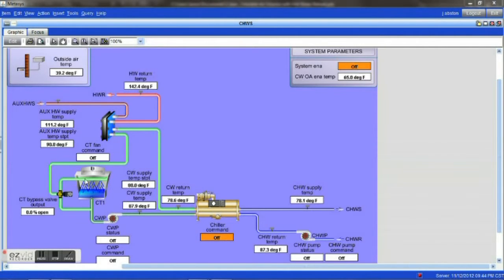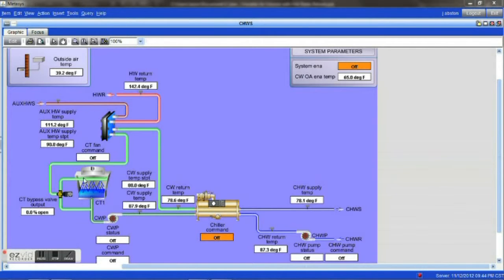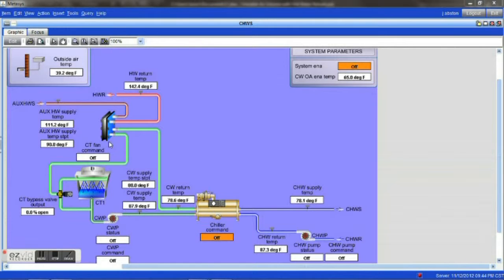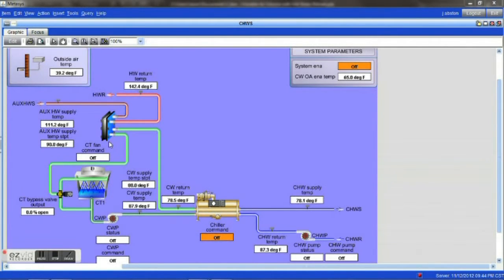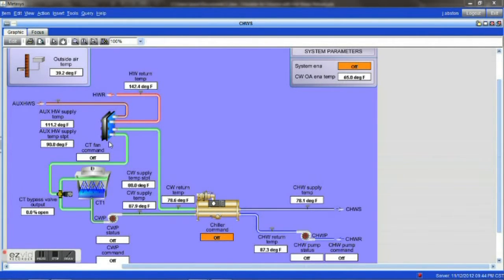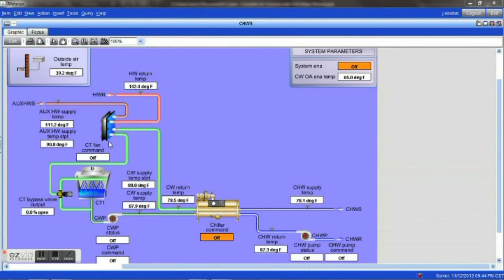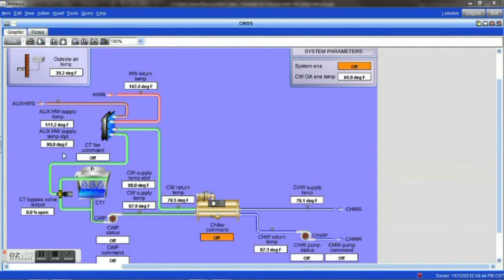In fact, that's why we still have a cooling tower in a lot of them to have a place to relieve that excessive heat. Now, another thing is, if you are running in an economizer mode during the cooler time of the year, you also have to think about how you're going to generate heat then. If you're going to use some type of a boiler or steam system or some other type of hot water system.